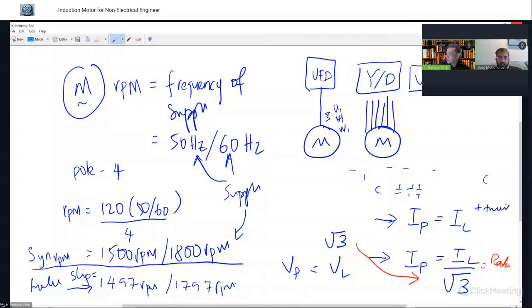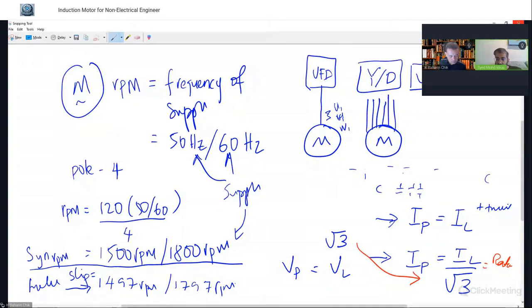Alright. And regarding the frequency and the RPM just now, someone asked: sometimes I see the motor nameplate rated 50 or 60 Hz, but in the VFD someone said to run it at 100 Hz. Can the motor actually run beyond 60 Hz? Beyond the rated? In fact, let me see. I'll draw a new one.